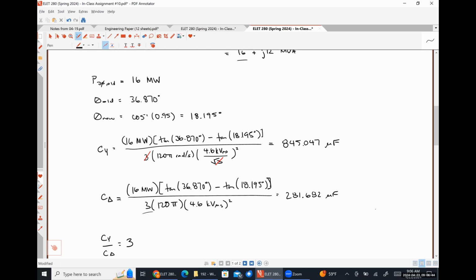You can connect a synchronous motor in such a way that it represents a capacitive load. However, connecting the synchronous motor in that way is usually done to provide power factor correction for all of the other inductive loads. Inductive loads are what you are going to see the overwhelming majority of the time.